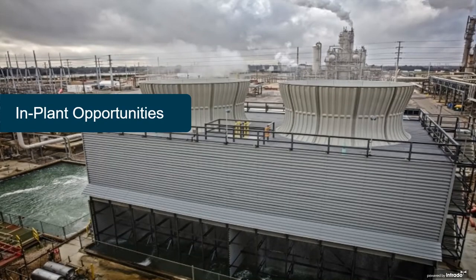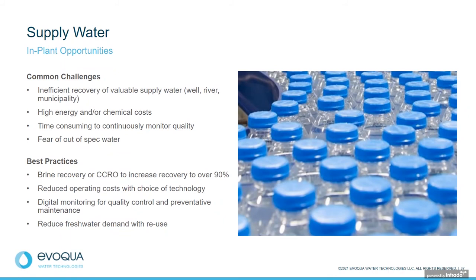All right, stepping through those in-plant, incremental savings things. We're talking about supply water, as I mentioned. This is about efficiency, it's about quality. So if you don't have a brine recovery RO and you can add one and increase your yield from 70% to 90%, that can have a large impact on hitting a sustainability target for a period of time.